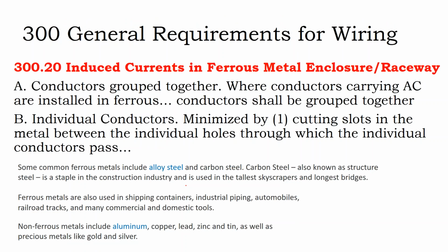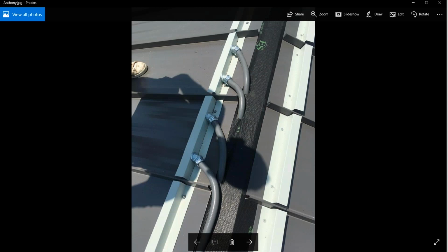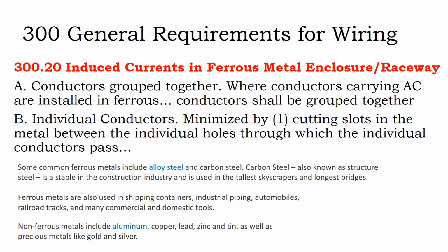Well, when we were building our internal pathway, one thing you would think of is, could our wires be heating up that metal through ferrous induction? It's more of an AC thing than a DC thing. So there are spacing requirements on conductors going through metal, and your knockouts that are pre-stamped into your metal should be sufficient for that.